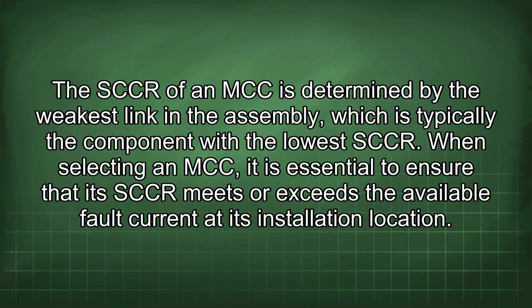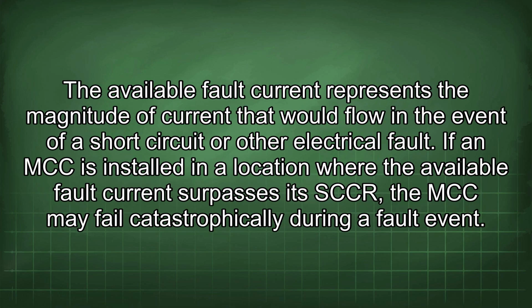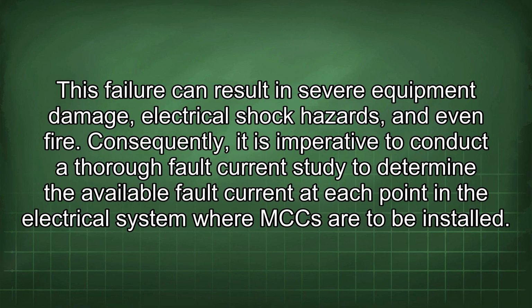The SCCR of an MCC is determined by the weakest link in the assembly, which is typically the component with the lowest SCCR. When selecting an MCC, it is essential to ensure that its SCCR meets or exceeds the available fault current at its installation location. The available fault current represents the magnitude of current that would flow in the event of a short circuit or other electrical fault. If an MCC is installed in a location where the available fault current surpasses its SCCR, the MCC may fail catastrophically during a fault event. This failure can result in severe equipment damage, electrical shock hazards, and even fire.